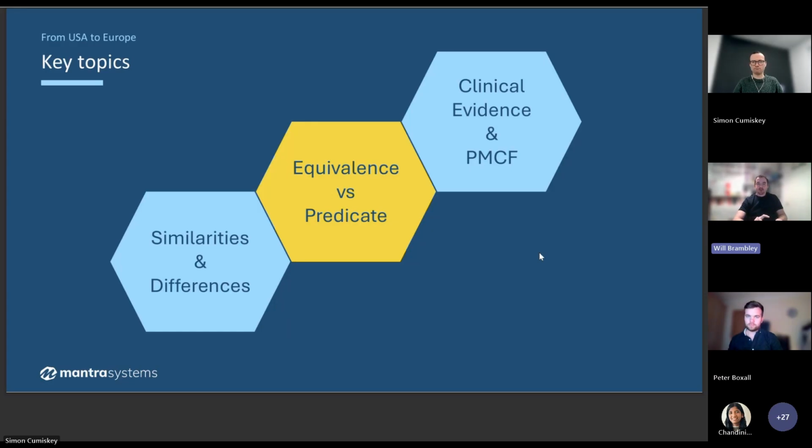Clinical characteristics relate more to how the device is actually used with patients, and that's not something you have to really consider in an FDA claim of substantial equivalence, but things like, is it used for the same clinical conditions, the same patient population, and is it going to be used by the same kind of user, whether that's a lay person or a specific healthcare worker. So ultimately, you've got to try and make sure that you're addressing all three of those areas.